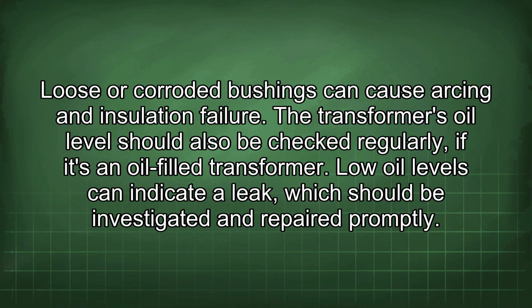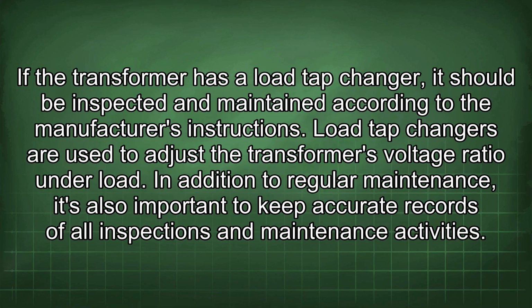The transformer's oil level should also be checked regularly if it's an oil-filled transformer. Low oil levels can indicate a leak, which should be investigated and repaired promptly. If the transformer has a load tap changer, it should be inspected and maintained according to the manufacturer's instructions. Load tap changers are used to adjust the transformer's voltage ratio under load.